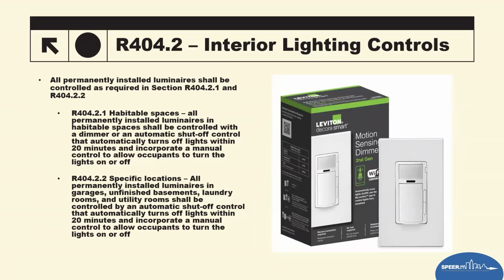A lot of jurisdictions don't really enforce this or have this as part of their code, but it is in the code book where you're using interior lighting controls. So all permanently installed fixtures must have either dimmer or automatic shutoff controls. For habitable rooms like living rooms, bedrooms, dining rooms, dens, the controls must be able to dim the lights or automatically turn them off within 20 minutes after an occupant leaves. For non-habitable spaces like garages, unfinished basements, laundry rooms, utility rooms, the light must shut off automatically within 20 minutes.